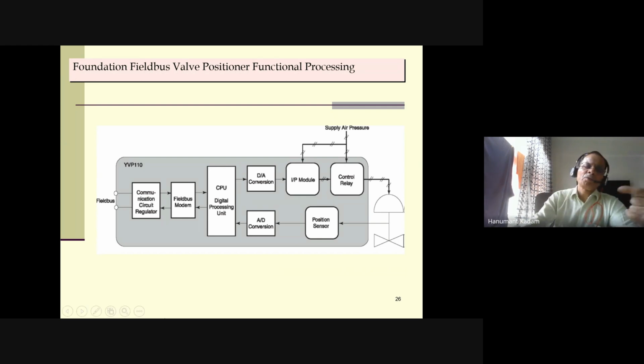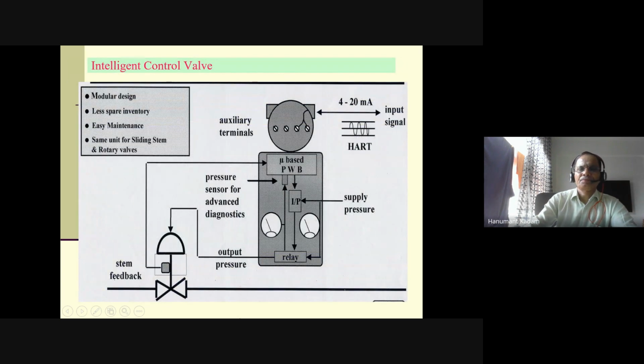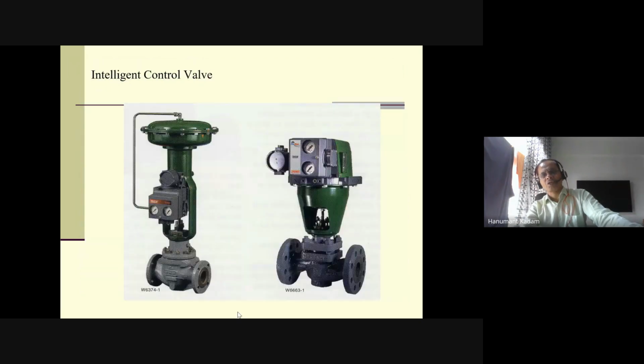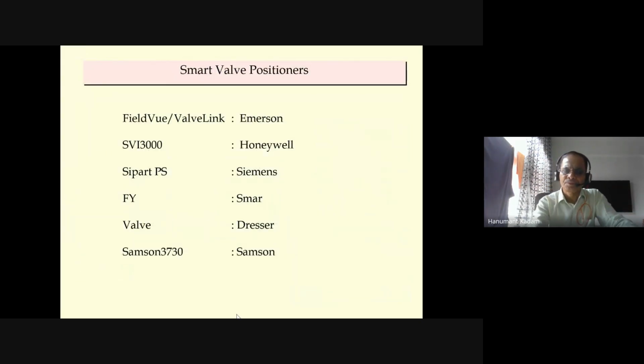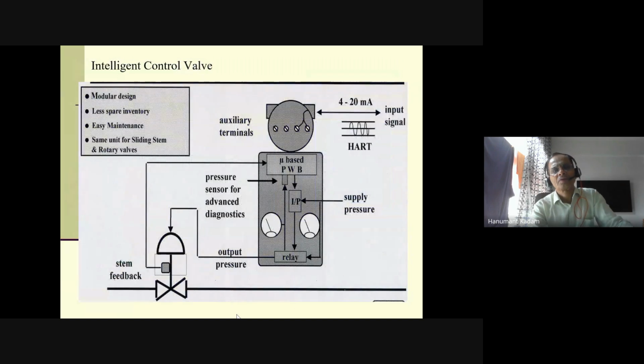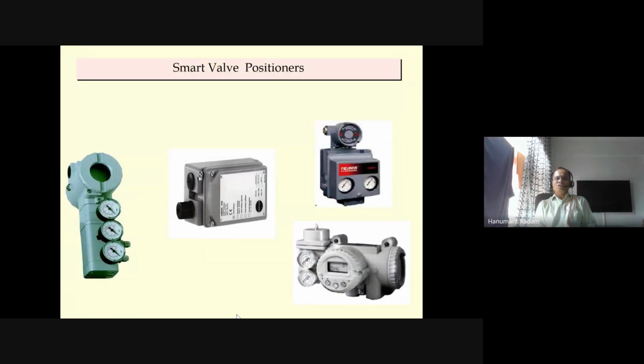Before going to the Foundation Fieldbus features, I'm first discussing the HART positioner. So HART positioner first we'll discuss. I'll come back to this picture. So smart means HART. HART is the communication protocol. Based on a HART communication signal, the valve positioners are designed. Therefore, it's called a HART positioner. I have shown in the plant picture also a HART positioner from Siemens, and there are a few other manufacturers' positioners here. You can see one, two, three, four.